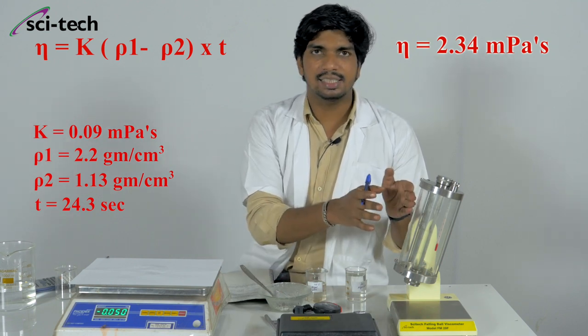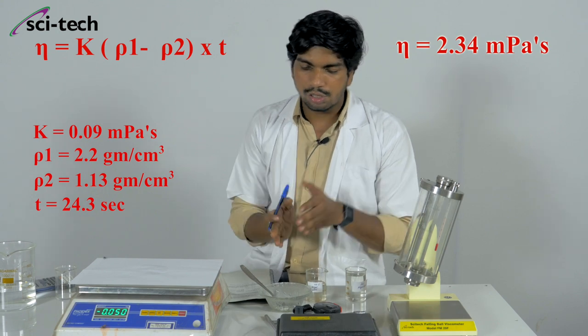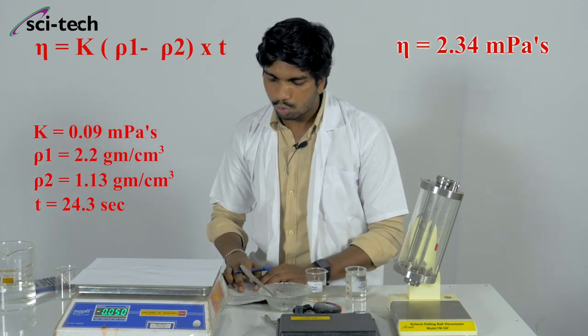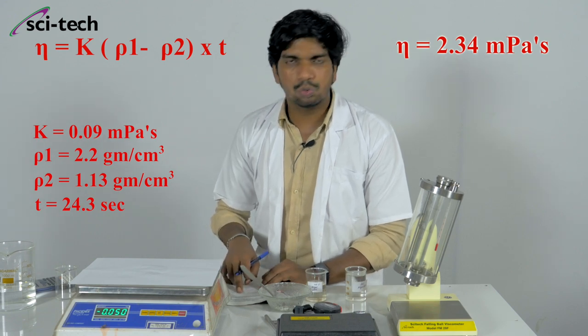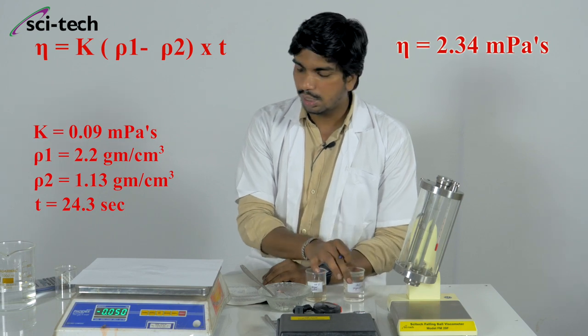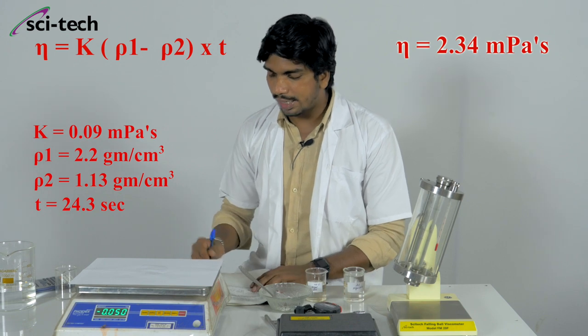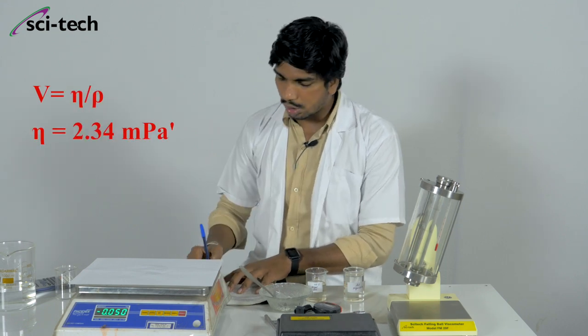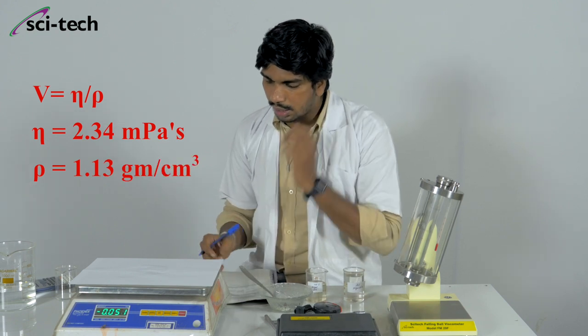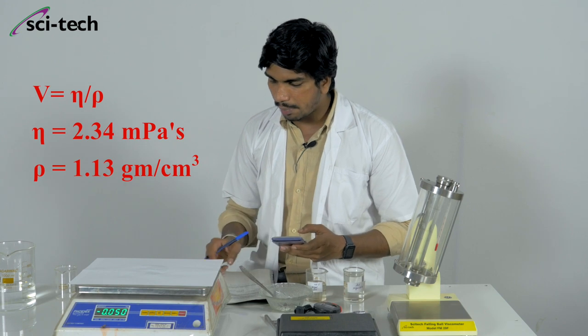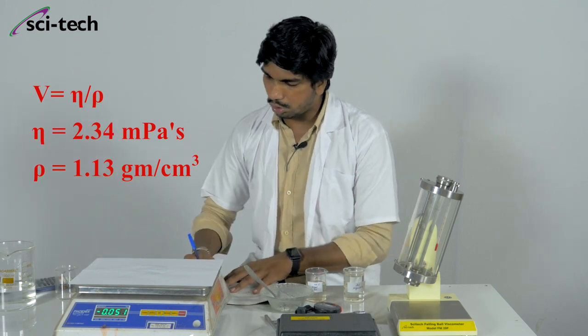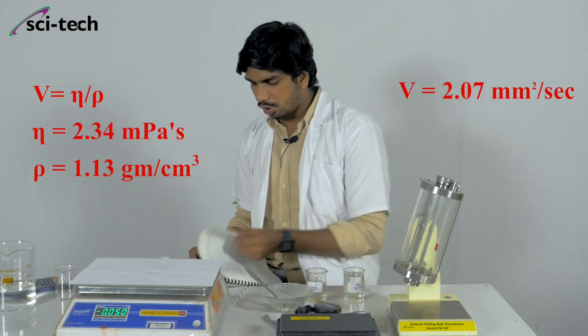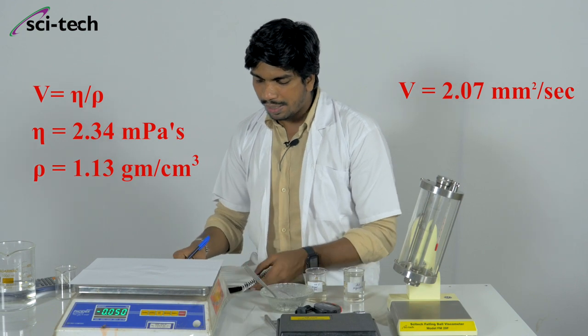At 30°C, for a 40% sugar solution made with 40 grams of sugar in 100 ml of water, using ball number 2 with a constant of 0.09 and density 2.2 g/cm³, we have calculated the dynamic viscosity to be 2.34 mPa·s. Now, kinematic viscosity equals dynamic viscosity divided by density of the solution: 2.34 ÷ 1.13 = approximately 2.07 mm²/s.